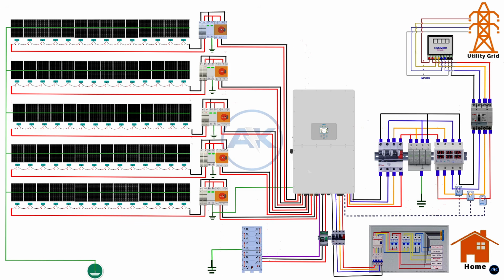Inspect the AC side. Confirm correct phase sequence, correct breaker ratings, secure neutral connections, and all AC isolators and MCBs in the off position. Verify the CT clamps are installed in the correct direction and securely connected. Use a multimeter to check continuity of grounding and to confirm there are no short circuits between positive and negative conductors. Make sure all cable routes are tidy, protected, and clearly labeled. Only after all checks are complete and confirmed should you proceed to system power-up and inverter configuration. This completes grounding and final safety checks.